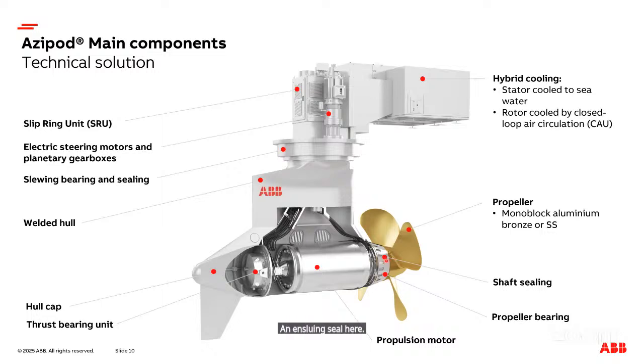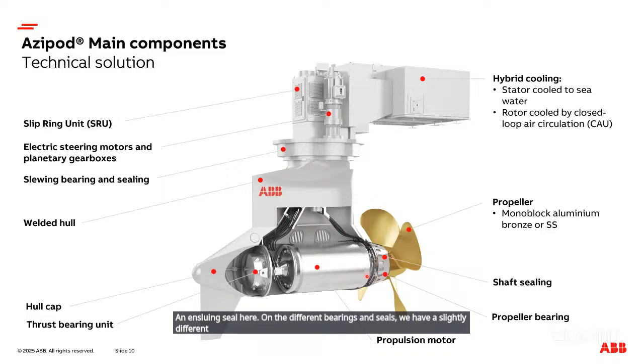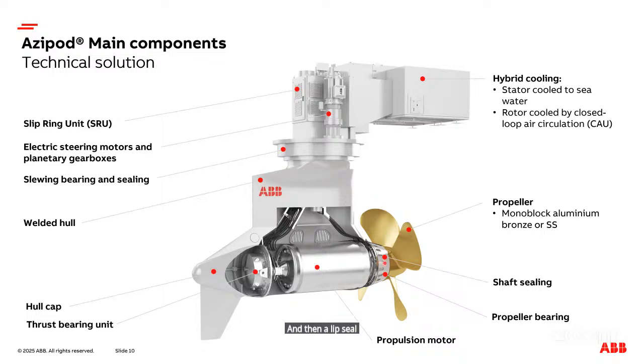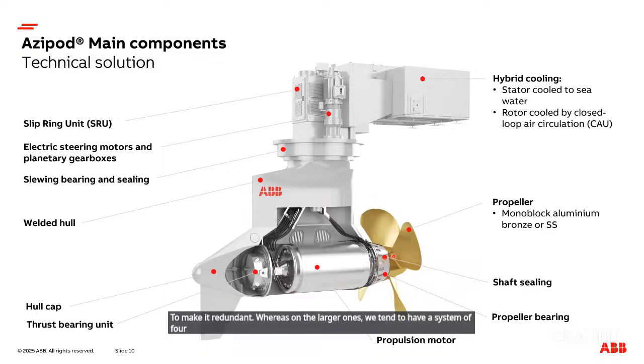On the different bearings and seals, we have slightly different solutions in different products. For the smaller ones, we tend to have a face seal and then two lip seals as a double to make it redundant, whereas on the larger ones, we tend to have a system of four lip seals to govern the sealing.